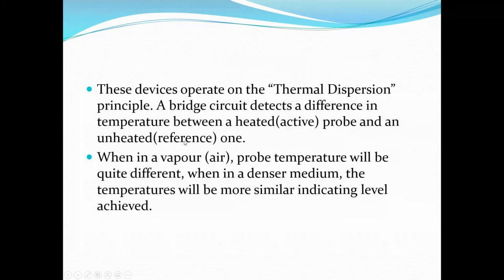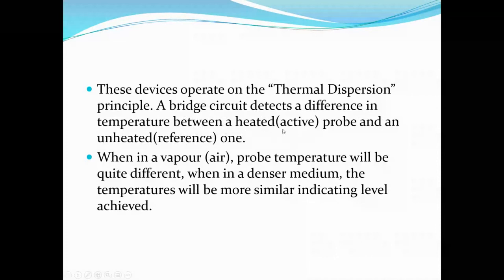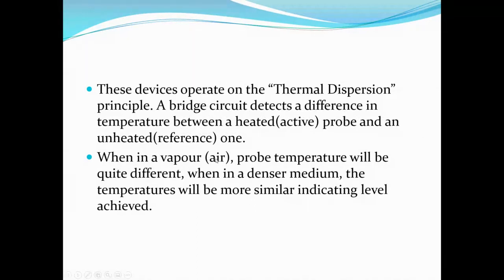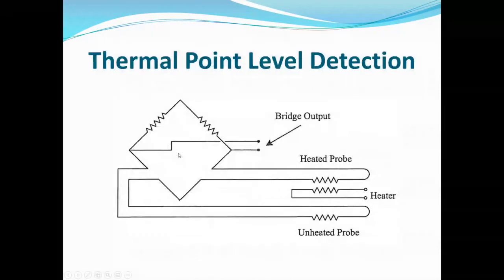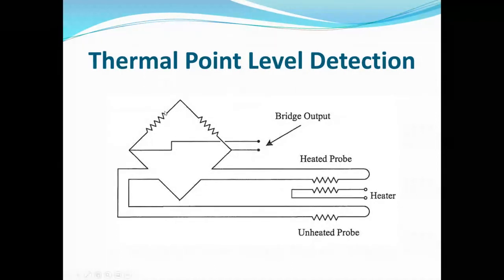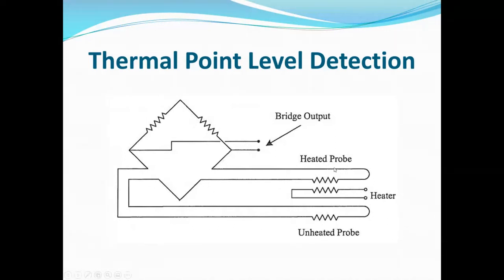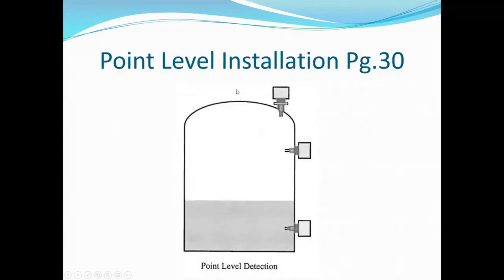Thermal dispersion devices operate on the thermal dispersion principle. A bridge circuit — the Wheatstone Bridge — detects a temperature difference between the heated (active) probe and the unheated (reference) probe. In vapor or air, probe temperatures will be quite different; in a dense medium, temperatures are more similar, indicating the level has been reached. Used for point level detection, just like any other switch — where you put it is where it works: vertically, horizontally, whatever the application requires. No real calibration per se — it's either thermally different or it's not.